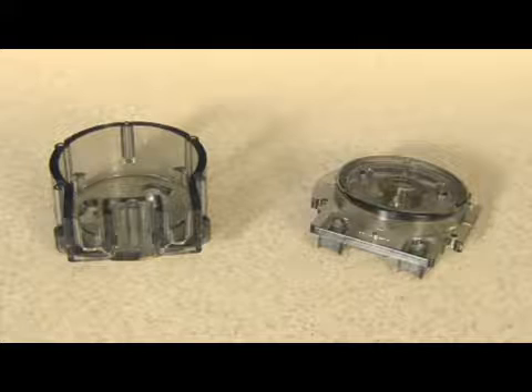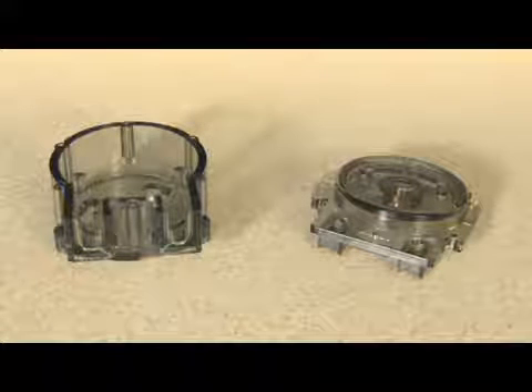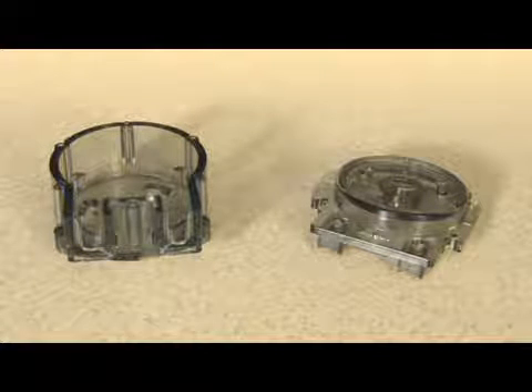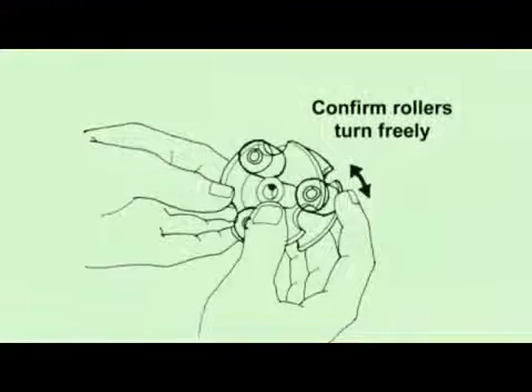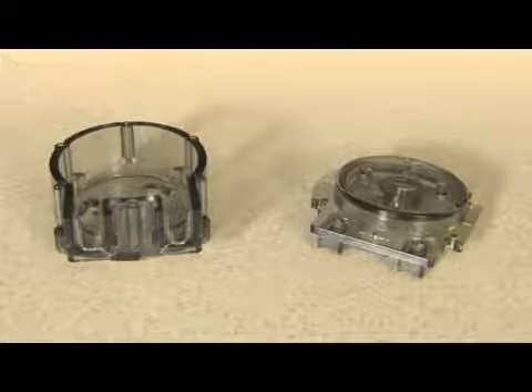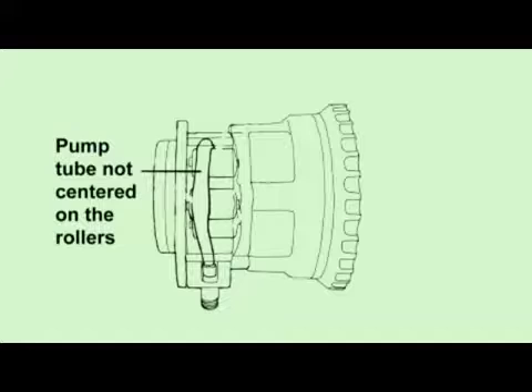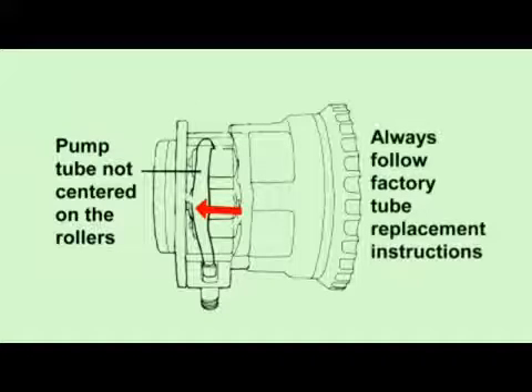In the event of tube rupture, rinse the chemical residue with factory-recommended cleaners from the housing and roller assembly. The rollers in the roller assembly should turn freely. If the tube housing is cracked, replace it. The pump tube rubbing against the edge of the tube housing can cause the side to split. It is important to always follow the factory's tube replacement instructions, which include centering the tube on the rollers. The tube won't center if the rollers are worn or if the tube twists during installation.